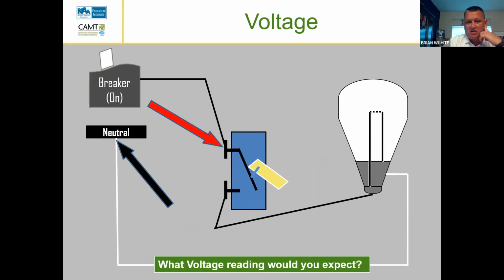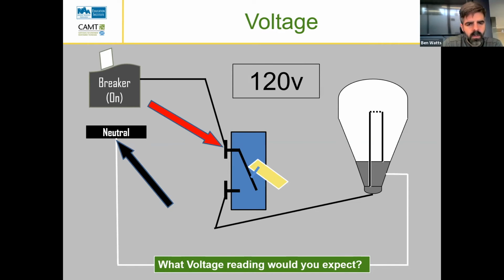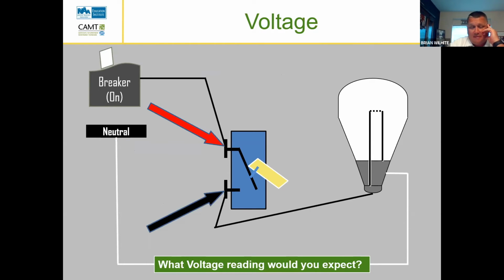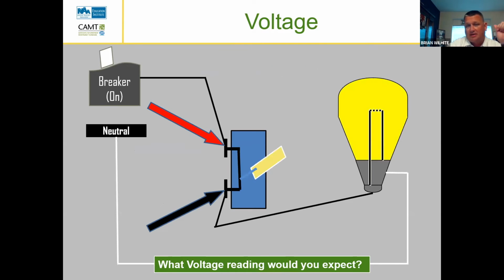So if we looked here, this is the question I just gave you: between our power going in and our neutral, how many volts are we going to have? 0. We'll have 120 there. 120 volts. Yeah, because that switch is open. So that black line feeding back to the bottom of the switch is still on our neutral side because we're not making that connection. And if I test it here, I'm going to get the same thing, another 120 volts, because that line is open. Now, if I make this switch, what am I going to get here now?